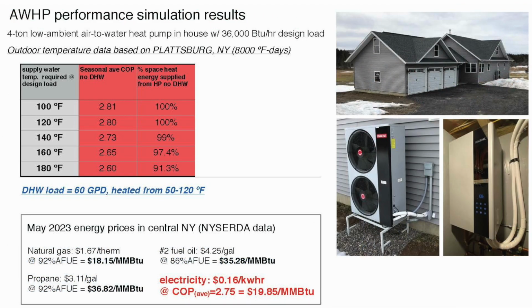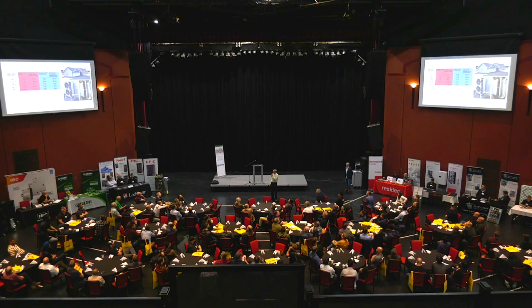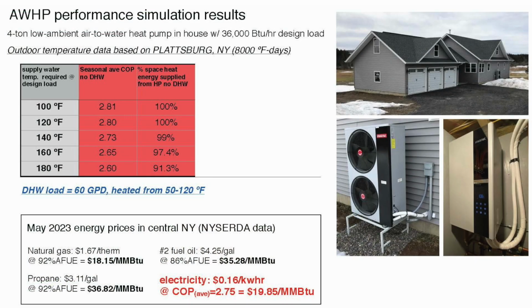Performance simulations. Now, this is a house in upstate New York. We did some performance simulations. Anybody know where Plattsburgh, New York is? Plattsburgh's way up there at the tip of New York State, and it's about an 8,000 degree day climate. It's cold. And so we did performance simulations on air-to-water heat pumps. And I'll cut to the quick. We're seeing COPs, these are average COPs, from 2.8 down to about 2.6.